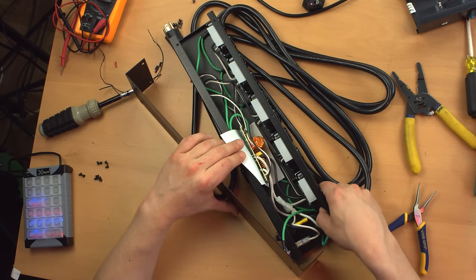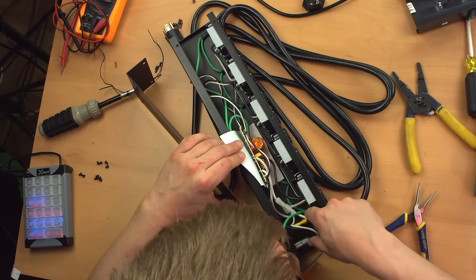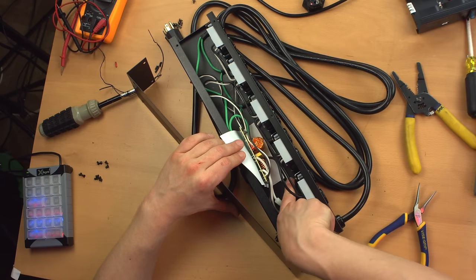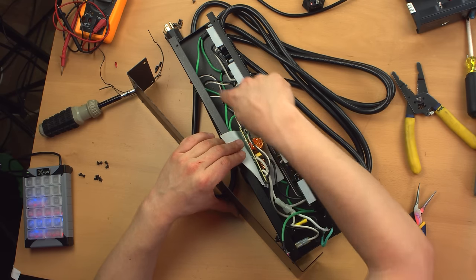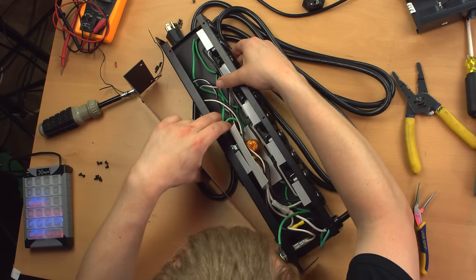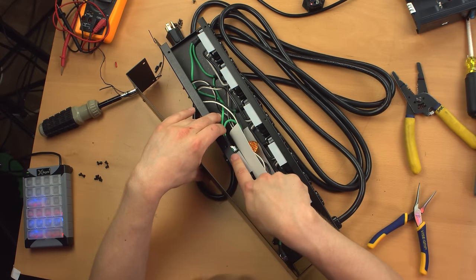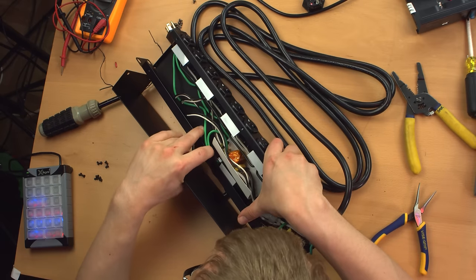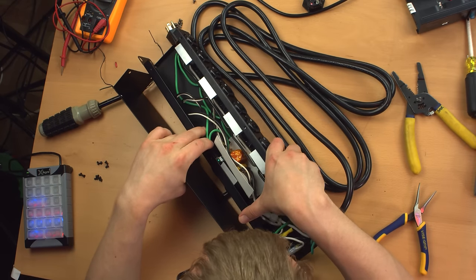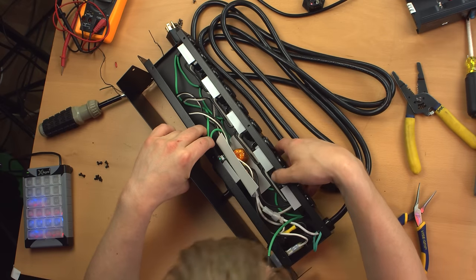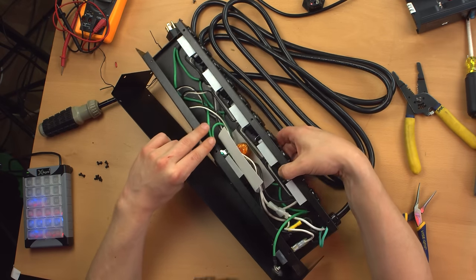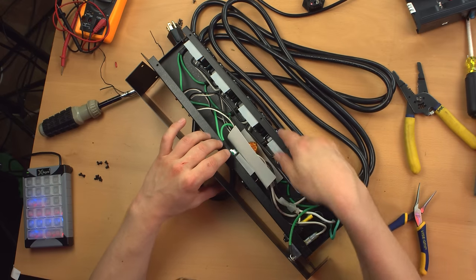And then it looks like the grounding wire is looped into each receptacle unit individually, and then comes back around to the front receptacle unit, where it's got a nice heavy lug on the end of the green wire. And yeah, see, this is very well made. This is what you'd want to see in a PDU.